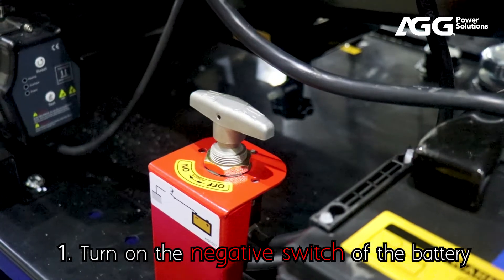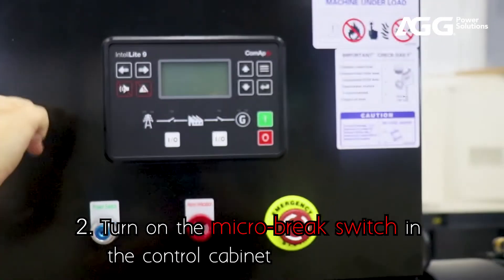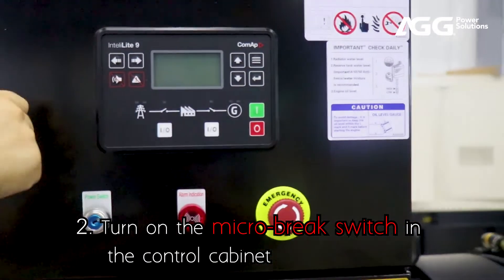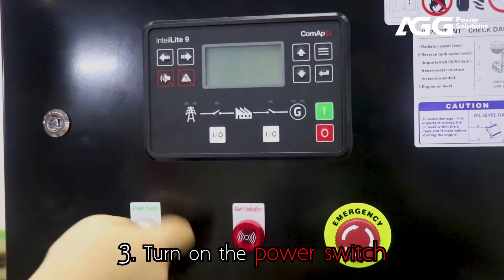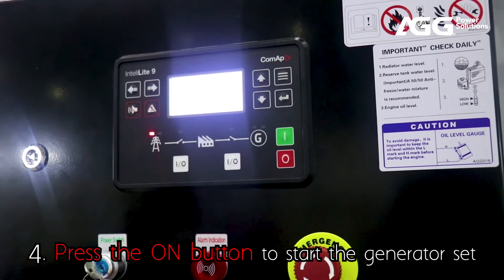1. Turn on the negative switch of the battery. 2. Turn on the micro-break switch in the control cabinet. 3. Turn on the power switch. 4. Press the on button to start the generator set.